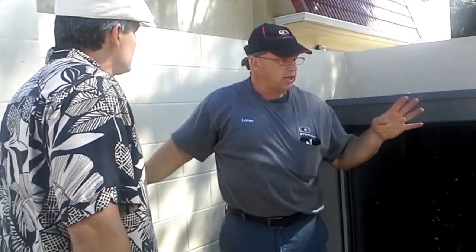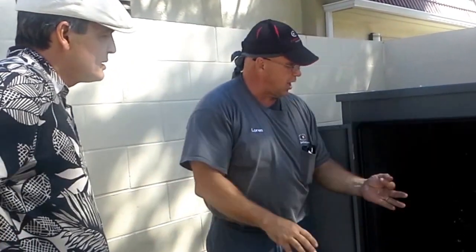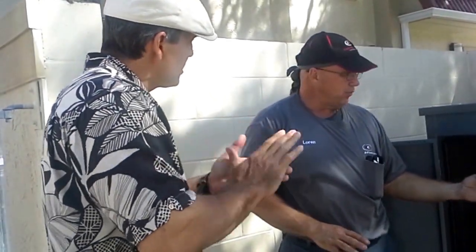In other words, it's taking the load from whatever backs up and transferring it to the alternator. That's exercising your transfer switch. It's letting you know that it can carry the load and the transfer switch is working. You know that it's starting to generate, and it's warming everything up. It's exercising everything. That's why I like doing it with a load. Gas units heat up pretty quick, and you want to bring it up to the maximum temperature for 5 or 10 minutes. This is a gas unit, a smaller unit. A 15, 20-minute exercise every other week would be minimal to do it.